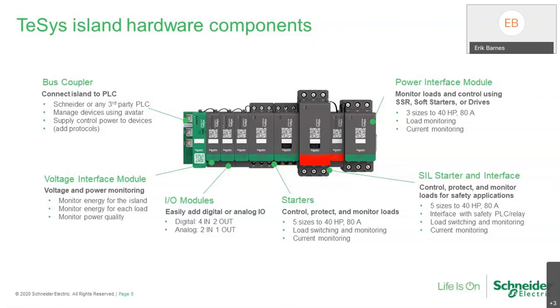We have starters, which are doing your controlling, your protection, and your monitoring. And we have basically five sizes, five part numbers, if you will, up to 40 horsepower, 480 volt or 80 amps continuous current. So it's a very limited number of SKUs that cover a wide range. Then we have a safety starter version, which is used in safety applications. We have some potential machine hazards, depending on what you're using and what you're doing. This meets all the IEC safety standards, and we include an interface for you to use as well. The interface will allow you to talk to your safety PLC or your safety relay, to get that permission signal to then allow that starter to pull in.